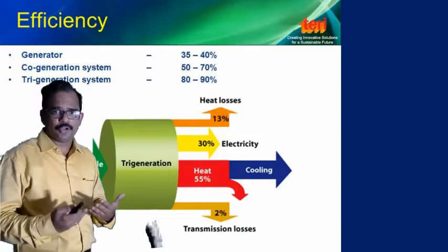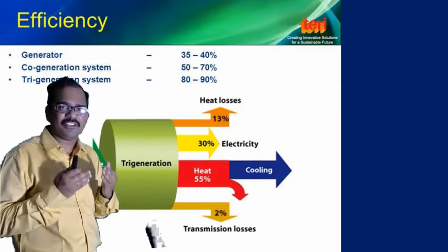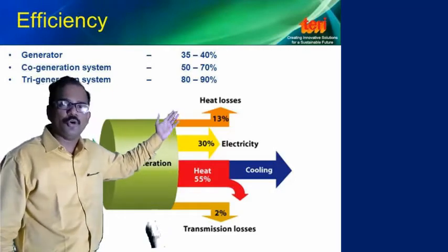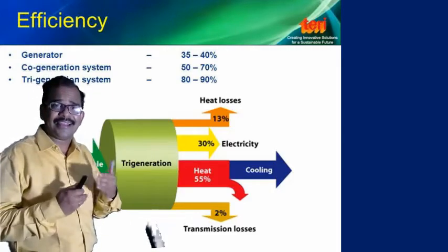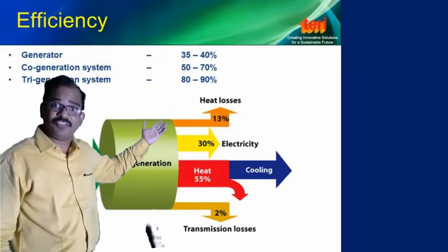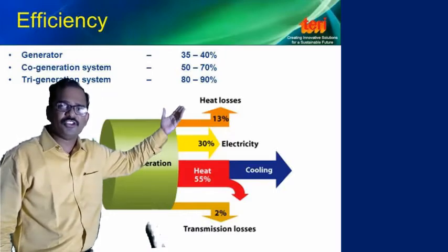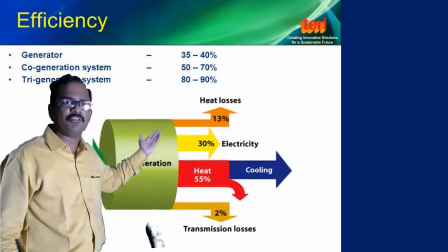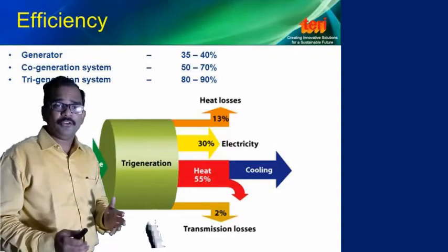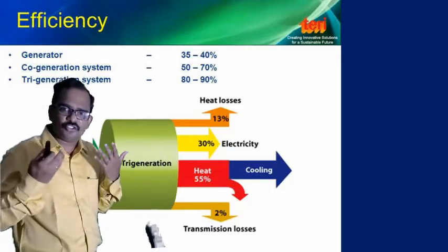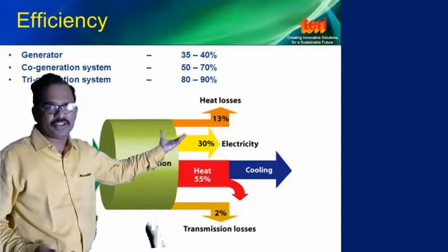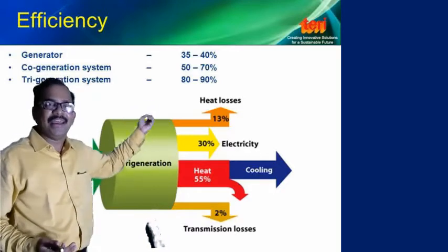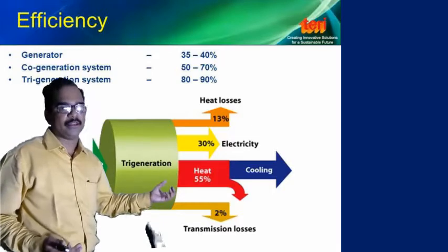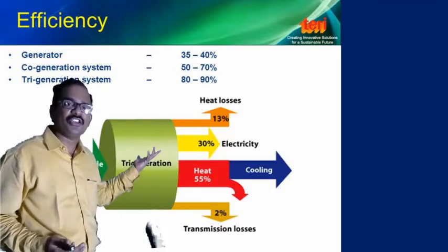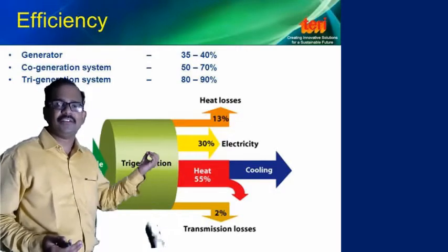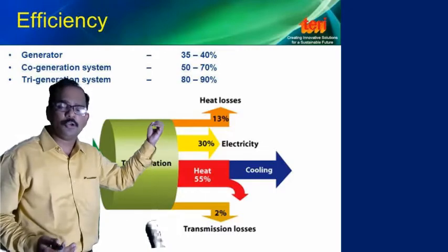Coming to the efficiency point of view, in order to generate the electrical energy by means of a generator, the efficiency will be around 35 to 40%. Whereas to generate the electricity and heat by means of a cogeneration system, the efficiency is 50 to 70%. Here the efficiency improved because we are utilizing the same fuel for producing the electricity and heat. Now by using a trigeneration system, obviously the efficiency should be much higher. It will be around 80 to 90% because we are using the same fuel for generating electricity, heat as well as the cooling, and thereby we are eliminating the extra fuel which is required for producing the cooling. That is why the efficiency is improved to about 85 to 90%.